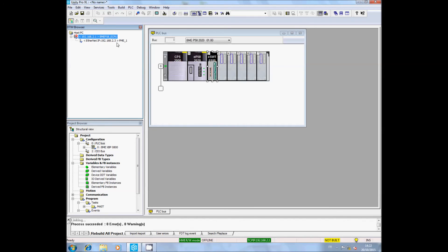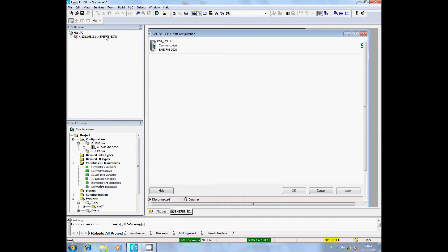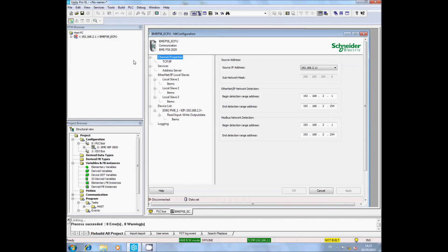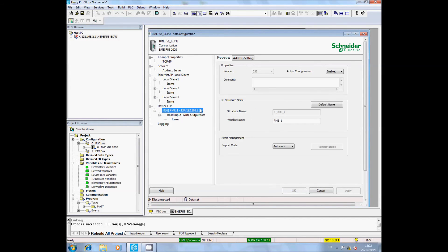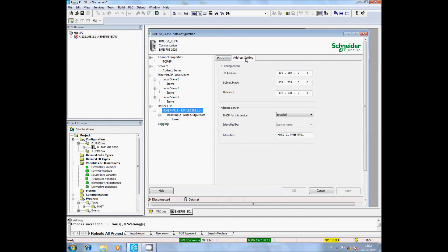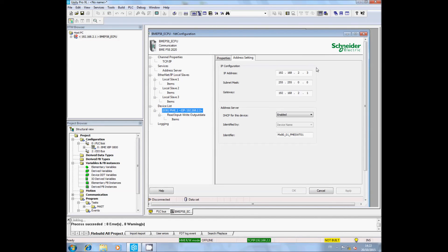Double-click on the CPU DTM. A line with the name of the PME SWT has been created. Select it. In Address Setting, fill in the address of the PME. It must be on the main network of the M580. If it is the first module added on the M580, the default IP address is the address of the CPU plus 2.